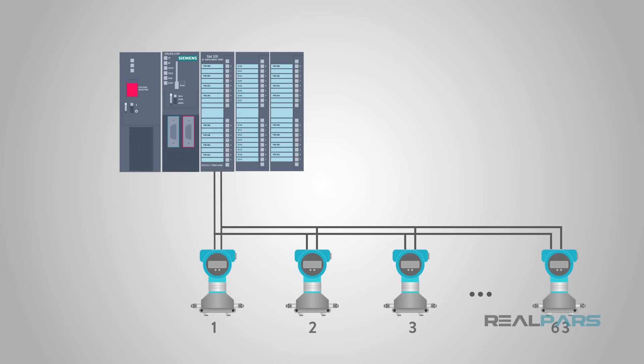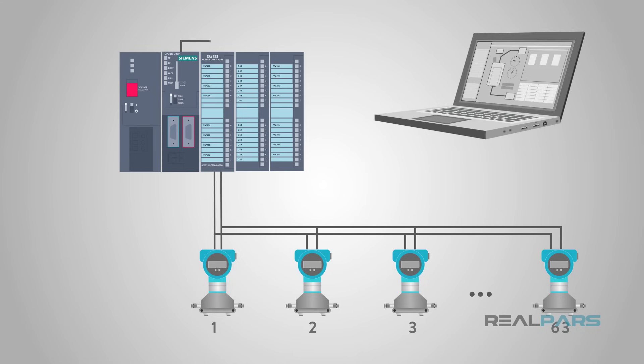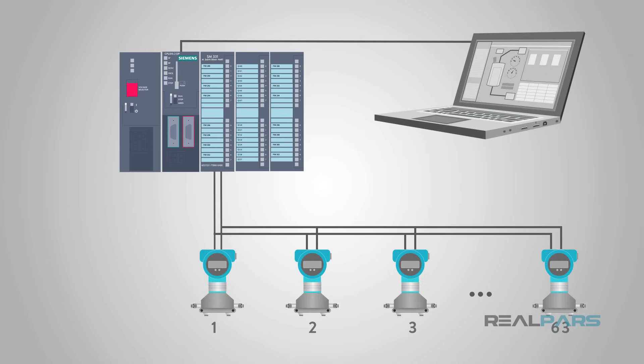The remote capability of HART sensors is very useful and powerful. In this diagram, we see a HART sensor connected to a PLC analog input card. We can access data in the sensor remotely using the HART communication protocol from the PLC programming software. That means we do not have to be at the location of the sensor to access its data.